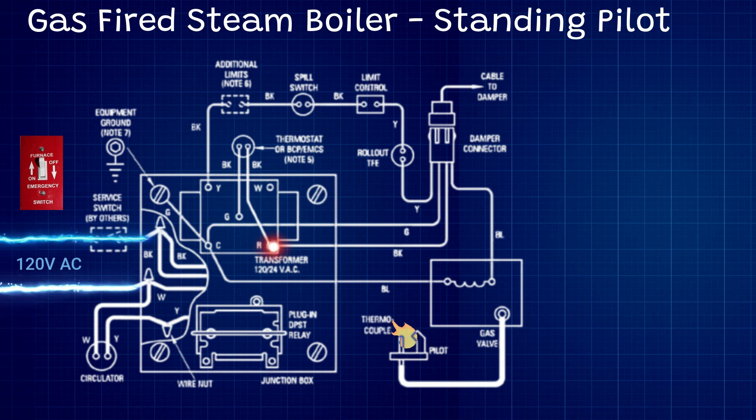What we have here is a schematic for a standing pilot gas fired steam boiler. We have our 120 volts coming in through our burner switch — our switch is on right now. We have 120 volts on one leg and the neutral on the other.